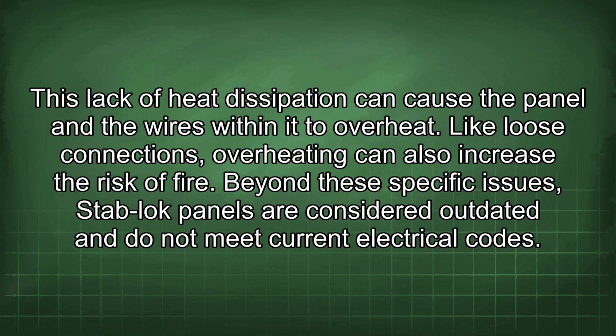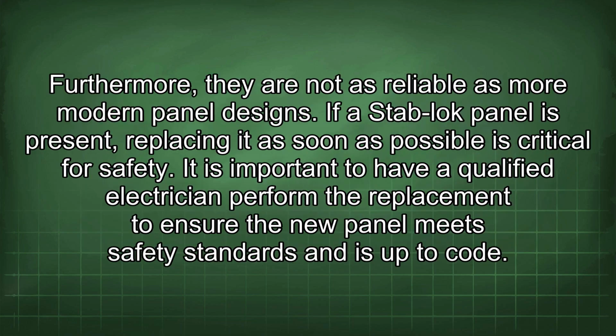Beyond these specific issues, Stab-lok panels are considered outdated and do not meet current electrical codes. Furthermore, they are not as reliable as more modern panel designs. If a Stab-lok panel is present, replacing it as soon as possible is critical for safety. It is important to have a qualified electrician perform the replacement to ensure the new panel meets safety standards and is up to code.